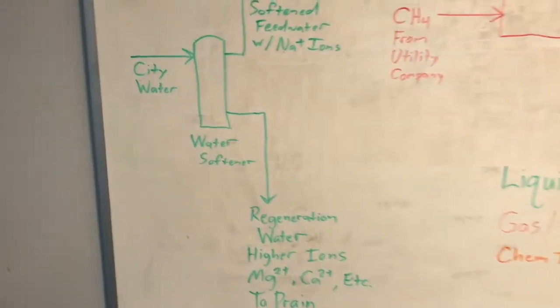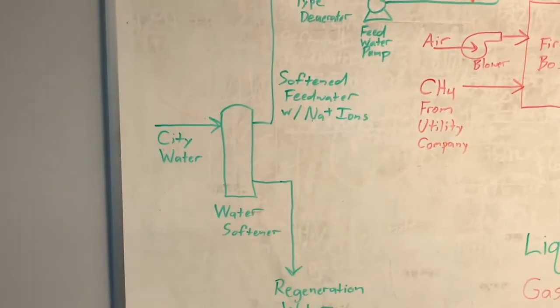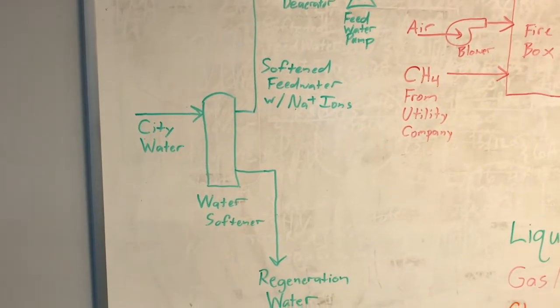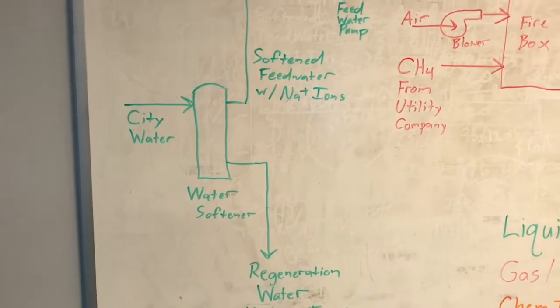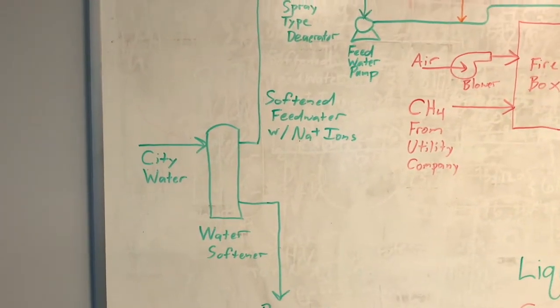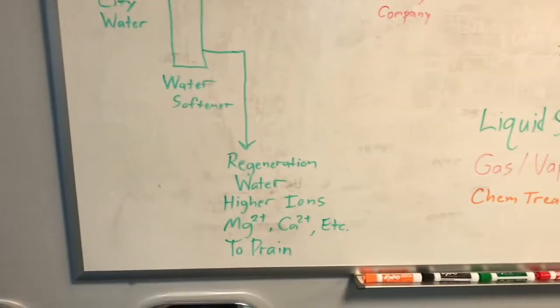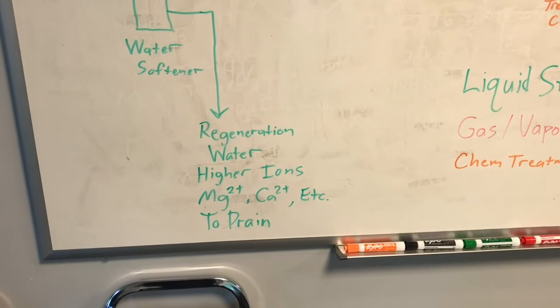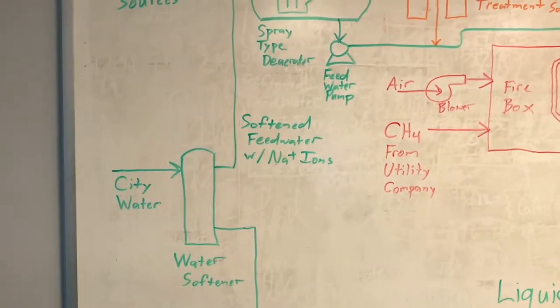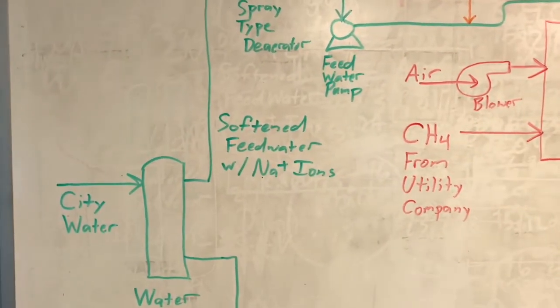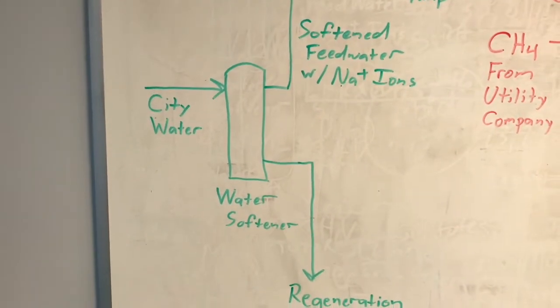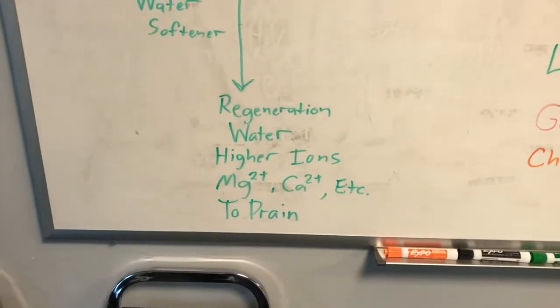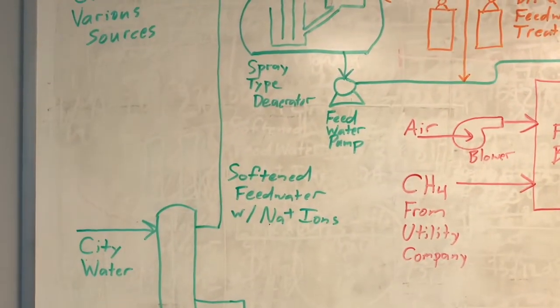It all starts with the feed water. We get city water from the city of Lock Haven, and it goes through a water softener system. The purpose of a water softener is to substitute the heavier ions that come in with the city water — such as magnesium and calcium, which cause scaling issues in boilers — and replace them with softened sodium ions. This goes through a regeneration purge cycle with a salt brine solution, which displaces these ions and moves the softened water through.